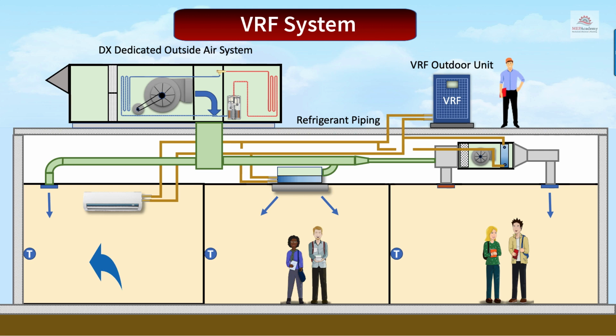This takes the burden of treating the ventilation air off of the VRF fan coils, which will handle the room load. The DOAS can provide heating and cooling of the outdoor air provided for ventilation. Conditioning outdoor air is energy intensive, and methods need to be adopted to avoid providing more outdoor air than is required by the spaces served. The DOAS will remove the moisture or latent heat and sensible heat from the ventilation air, allowing any downstream equipment to focus on the space sensible load only.